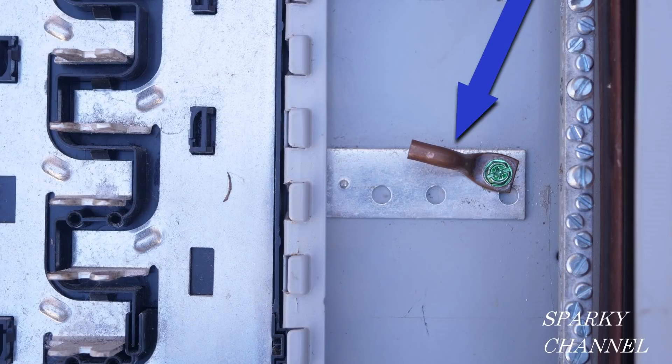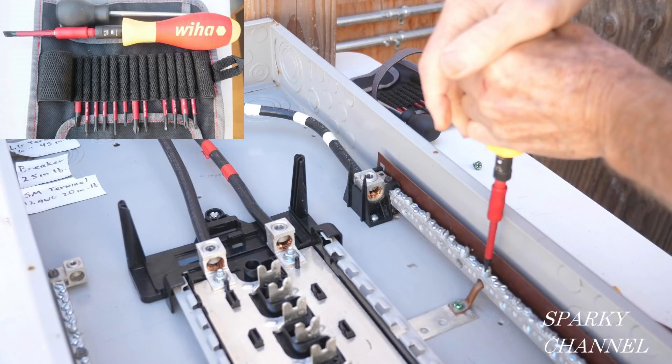If we wanted to use this panel as a sub panel, then we would need to keep the neutrals and the grounds separate. So our bonding strap would not be connected to the neutral bar, or better yet, we would remove the bonding strap to prevent any accidental bonding of the neutrals and the grounds.